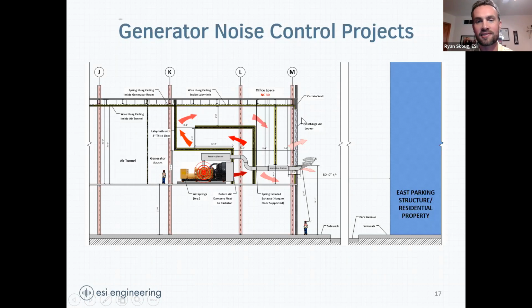Then it gets to this louver to go outside, because across the street was a potential residential receiver, which requires 50 dBA. Well, we've got this generator producing like 120 dBA, so we had to get all that noise around here and attenuate enough of it before it went outside.